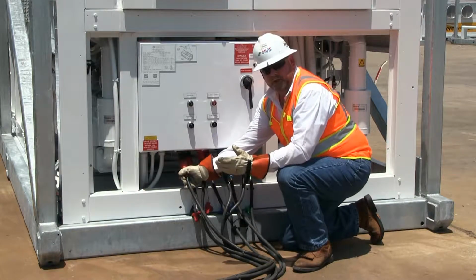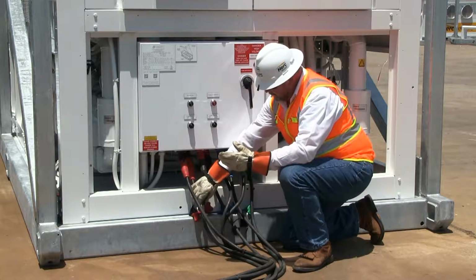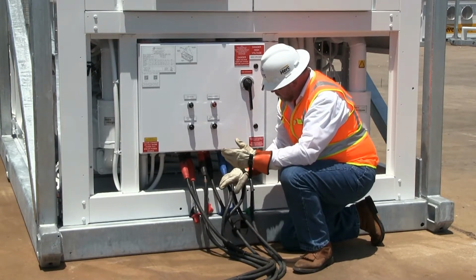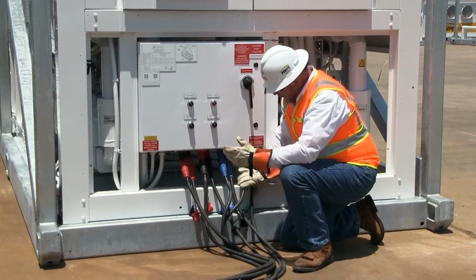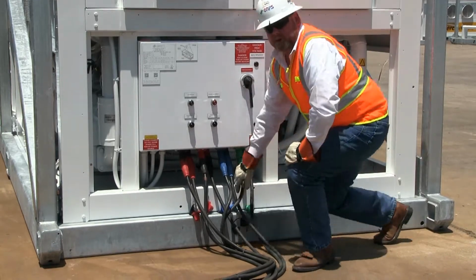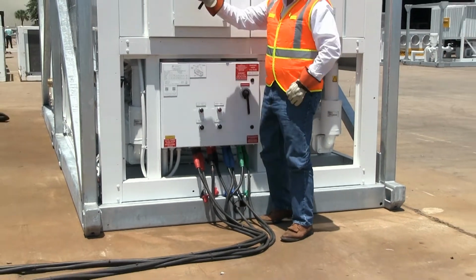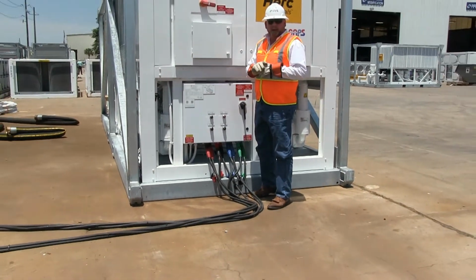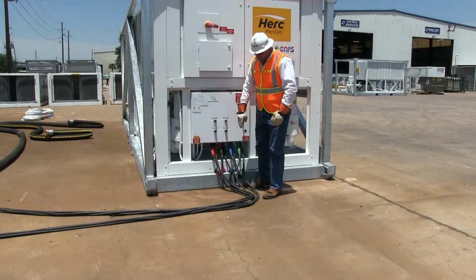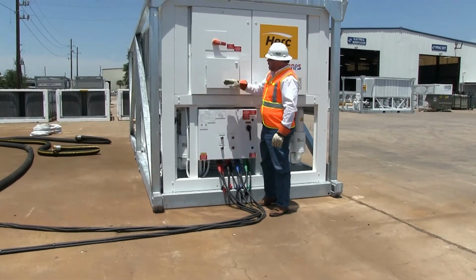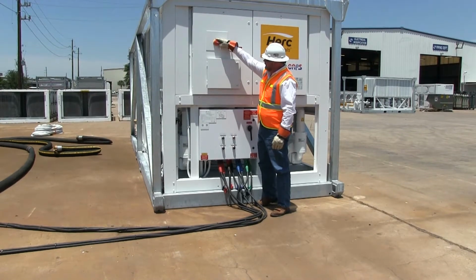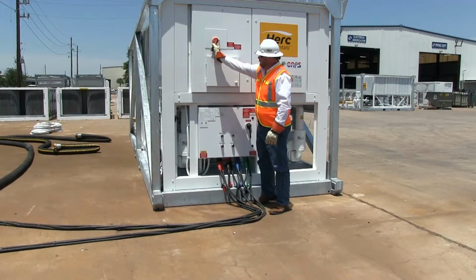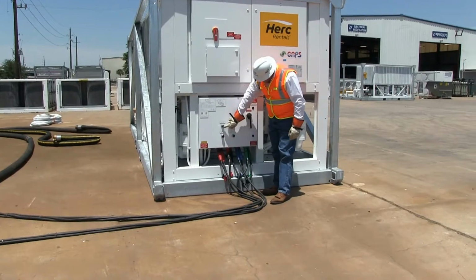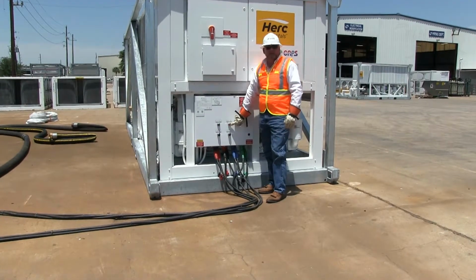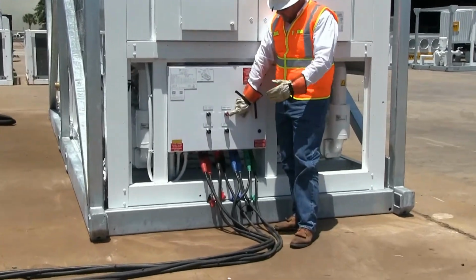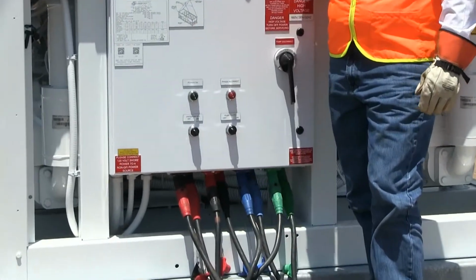Okay, we've completed hooking up both sets, so we're in a full parallel configuration here with L1, 2, 3, and our grounds. The next step is going to be for us to energize the power. We've removed our lockout tagout from our permanent power source, so the Camlocks are hot now, they are energized. We're simply going to take the main circuit breaker here on the chiller, and we're going to roll it around and turn it on. And you notice that we've got a power light here, but we also have a phase incorrect light. That indicates that two of our phases are backwards, they're out of phase.